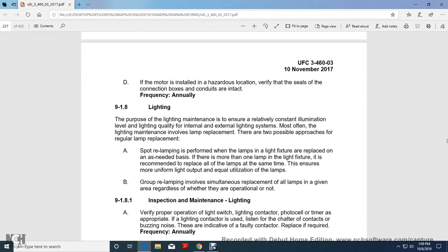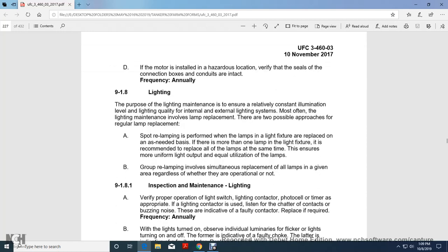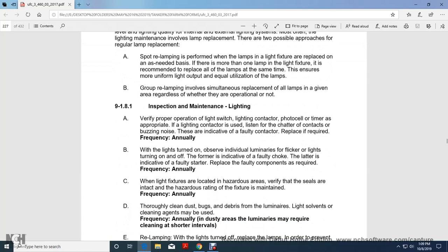There are two possible approaches for regular lamp replacement. Spot relamping, where the lamps or light fixtures are replaced as needed. On that basis, if there is more than one lamp in a light fixture, it is recommended to replace all the lamps at the same time to ensure more uniform light output with equal utilization of the lamps. Group relamping involves simultaneously replacing all the lamps regardless of whether they are operational or not.